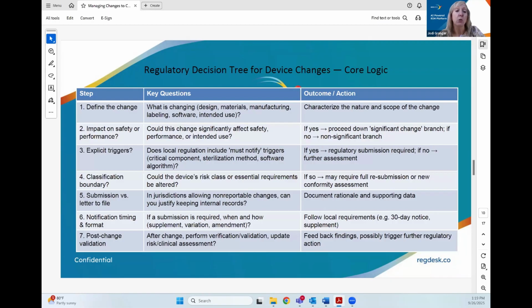Some of those include changes to critical components. If you're modifying your sterilization method, going from ETO sterilization to something else. Also, software algorithms can be significant as well, because if your software algorithm is modified and the validations are not done properly and demonstrated to show safety and effectiveness, there might be a risk to the patient. So it's really important to understand what those triggers are. The regulatory flowcharts that are provided are certainly helpful in doing that, helping you walk through that process.